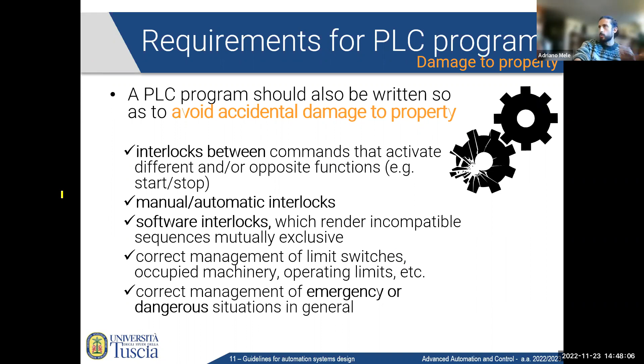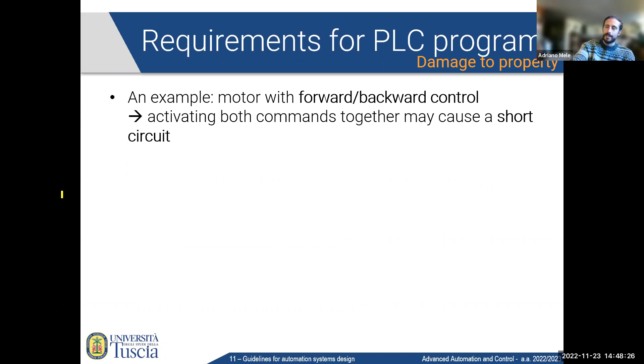Manual or automatic interlocks. Software interlocks, which render incompatible sequences mutually exclusive. This is like when we have seen the semaphore in SFC, that's a software interlock. If you are in one sequence, you cannot execute the other and vice versa. Of course, you need to manage correctly limit switches, occupied machinery, operating limits, and so on. And again, you need to manage correctly emergency or dangerous situations in general. That's a quite general prescription. An example, which we already did, but it's just written here, so let me comment on it quickly, is a motor with forward and backward control, where activating both commands may cause a short circuit. This is what we were adding to the exercise for the gate control last lecture.